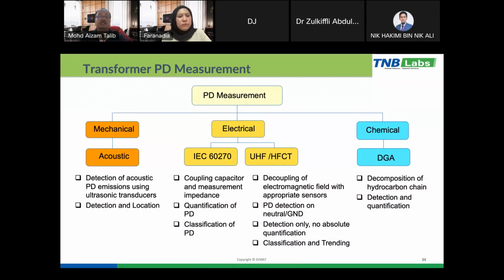power transformers. So, for the power transformer, the PD measurement normally we use the mechanical method, electrical. Either we follow the standard or non-conventional method using UHF, HFCT, and also TEV. And then the other method is what we call dissolved gas analysis.